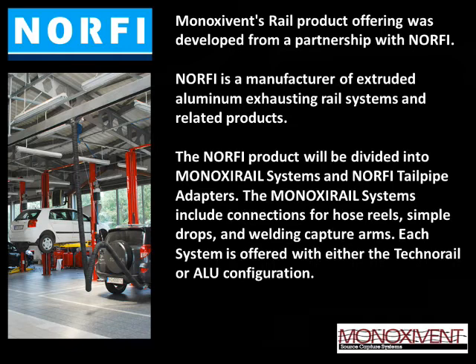Again, it's never 100%, so normally the diversity factor is going to be 30 to 40%. Say out of the 8 bays, he or she says, I never run more than 3 engines. So my next thought would be, do you want to just designate 3 bays and we'll outfit it with this equipment, and that's where you'll start vehicles. Again, normally they'll say, no, I have 8 bays, I need the ability to start an engine in any of the 8 bays.